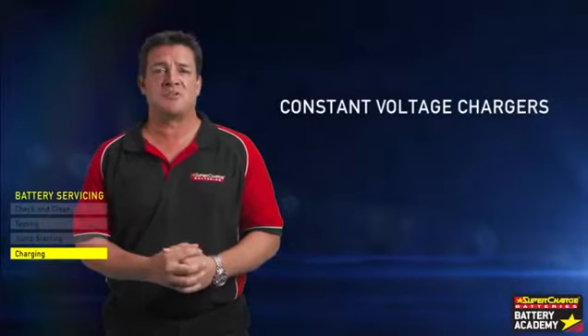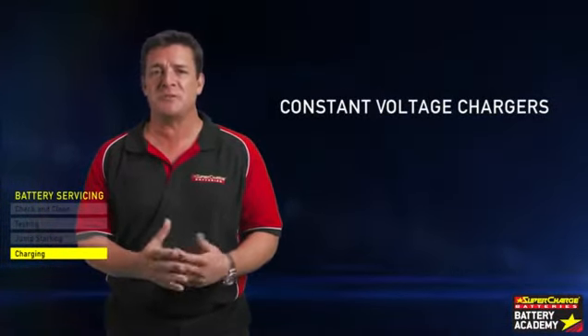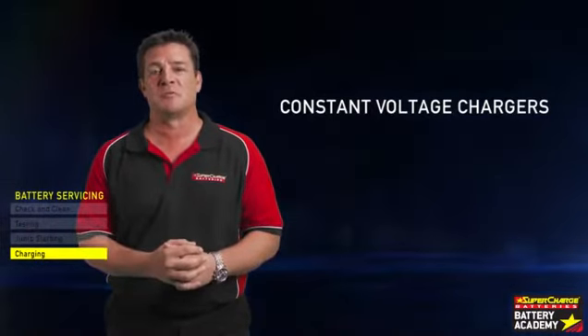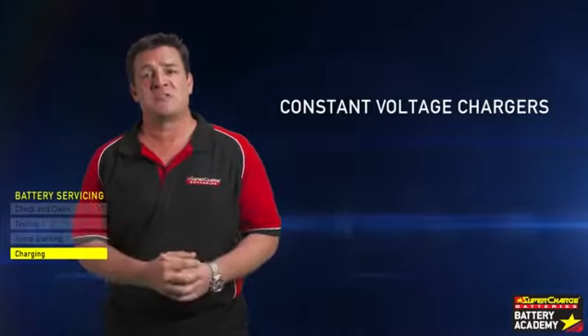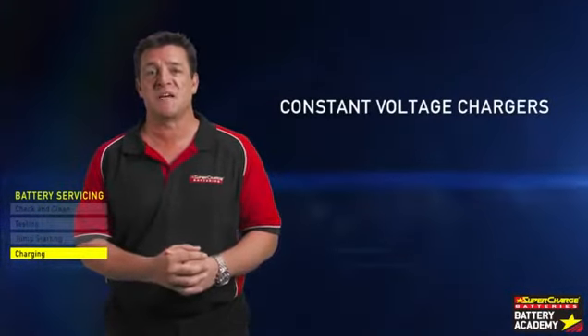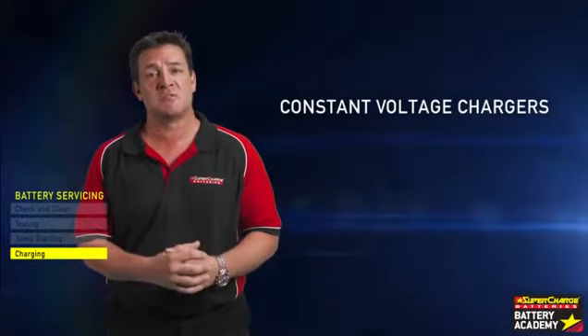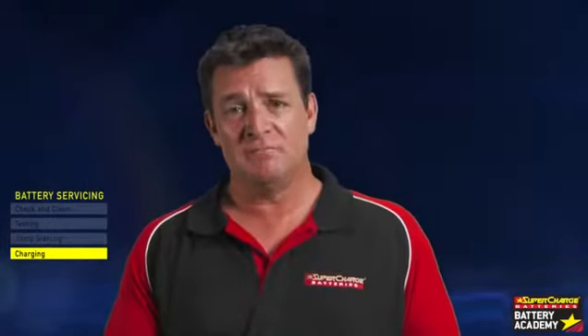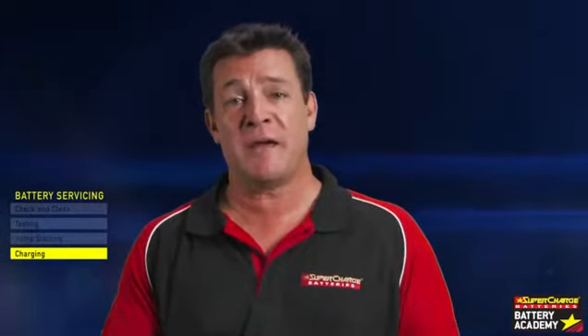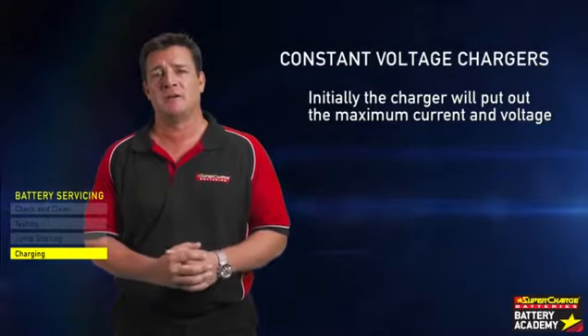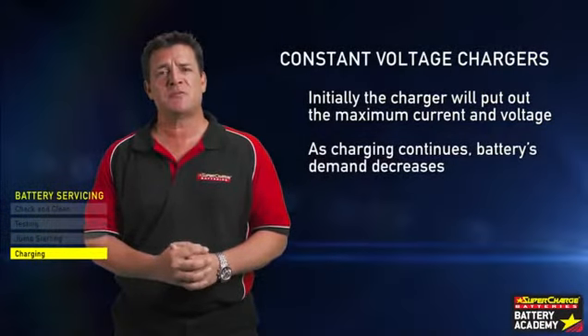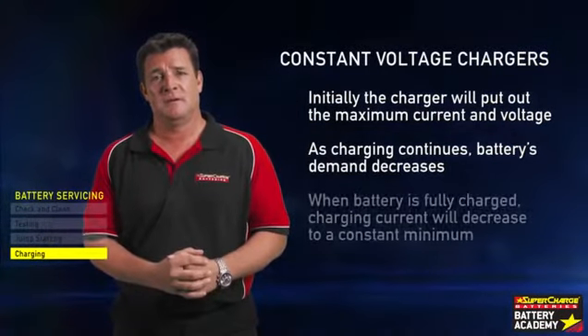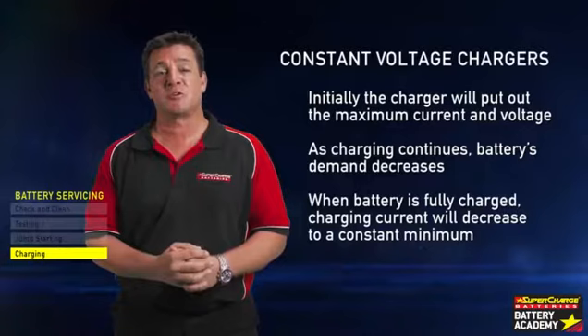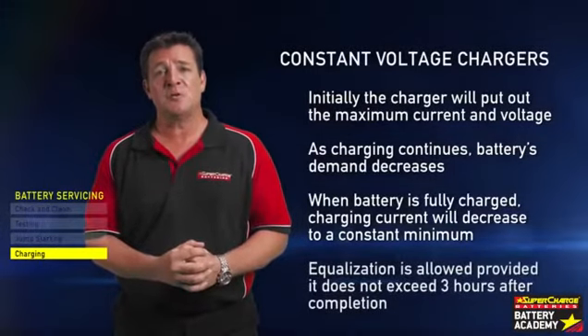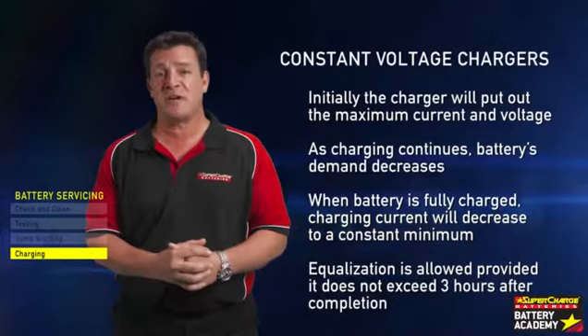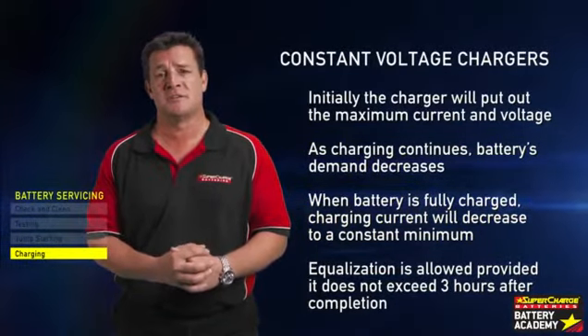Constant voltage chargers charge a battery at a design maximum charging voltage, usually above 13.8 volts and below 17 volts for 12-volt batteries. After a discharged battery has been recharged for a period of time and the desired maximum voltage is reached, the charger controls the charging voltage at a constant level. Initially, the charger will put out the maximum current and voltage demanded by the battery, and the charging current may be high. As the charging continues, the battery's demand for charging power decreases. When the battery is fully charged, the charging current will decrease to a constant minimum. Equalisation is allowed, provided it does not exceed 3 hours after the completion of constant voltage charge.